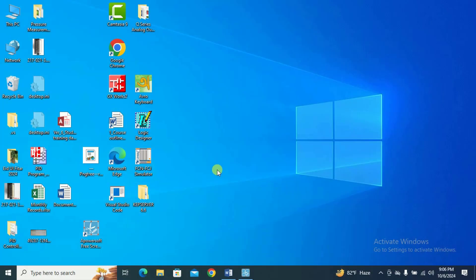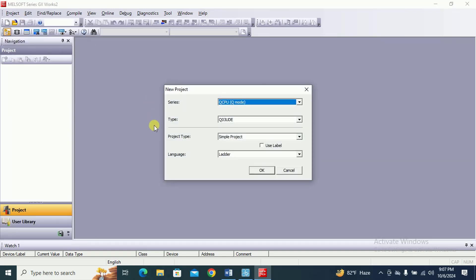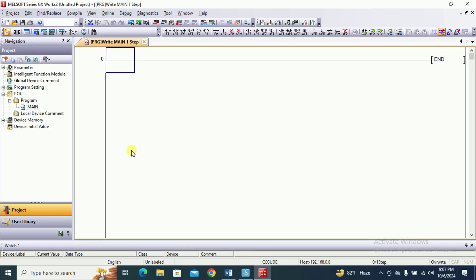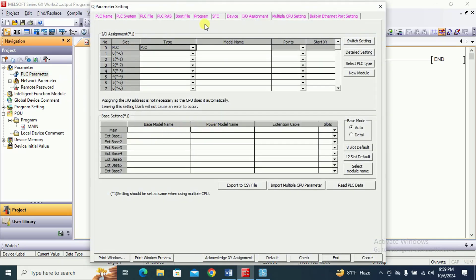Now let us proceed to the PLC ladder program for analog output using GX Works2 programming software. Open GX Works2 and create a new project. Select the CPU series as QCPU and the type as Q03UDE. Select the language as ladder language and click OK to finish creating the new project. Then go to parameter options and double-click on the PLC parameter tab to open the dialog box for Q parameter settings.